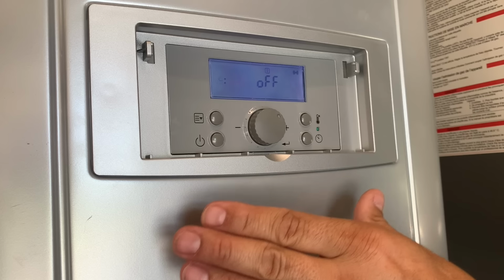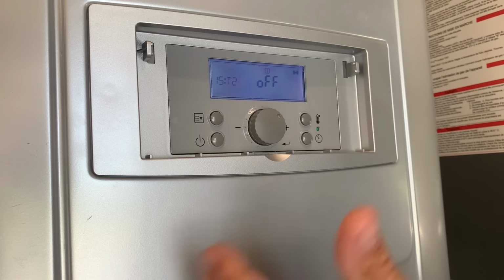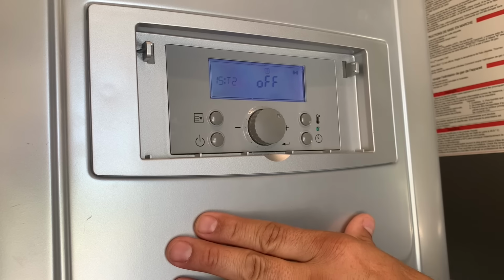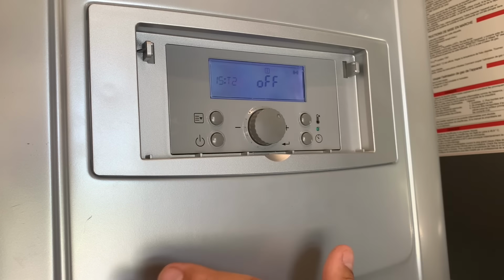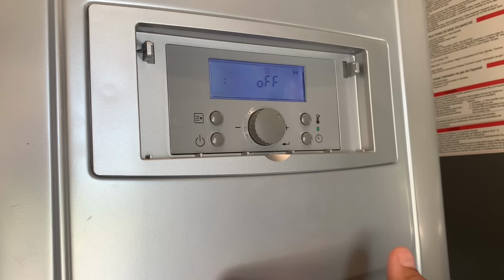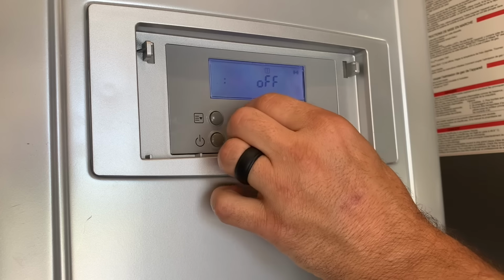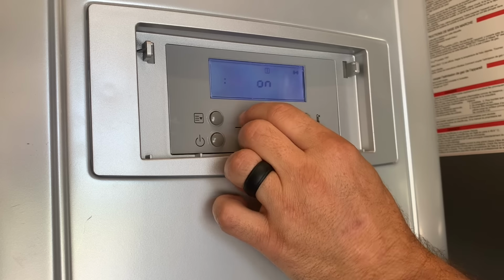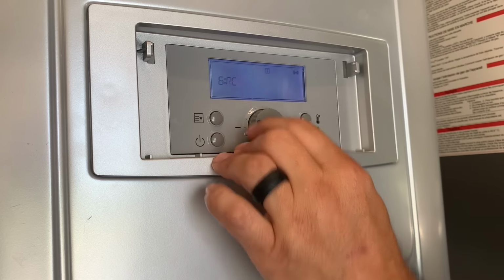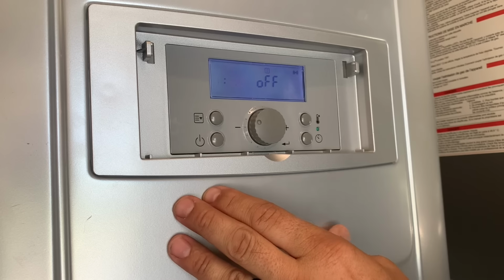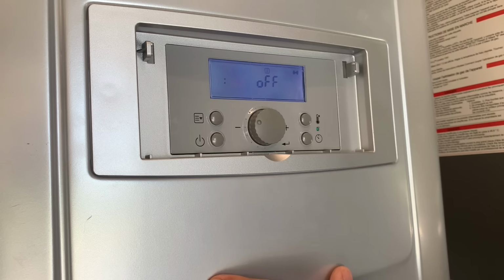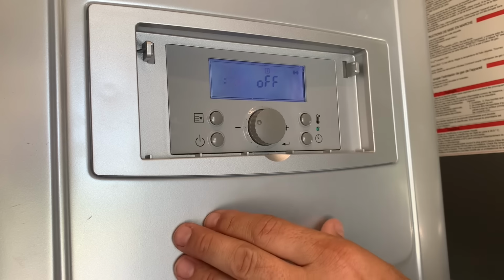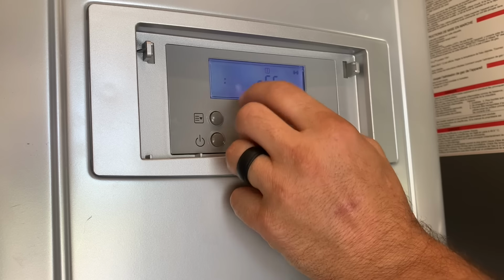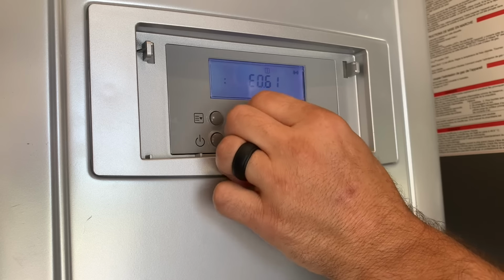If you have several bypasses in your system, more than one, if you have two, that could easily exceed the listed amount of feet length of pipe that this water heater will circulate through, and it'll throw that overheat code. Okay, you can bypass that by using an external pump with an aquastat or a timer. Go into your menu setting, go to 6RC and turn that off. And then you can set your external pump up, start circulating, have that on the timer of the aquastat, and it'll operate just like it would on a normal water heater. Okay, and that is the installer mode. That's all there is to that.